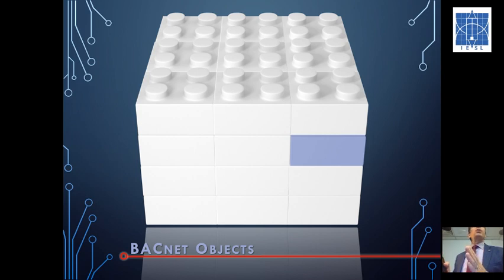A device on a logical network must serve information out. That information is what we call an object, which lives inside of our controller, or inside of our device. An object is a set of information or a particular sensor. So if we go back to our VAV controller that I mentioned just before, an object to a VAV device would be the temperature sensor. So the temperature sensor lives in the device.